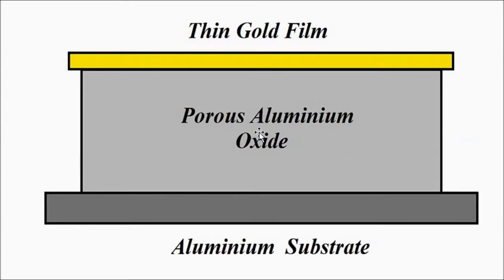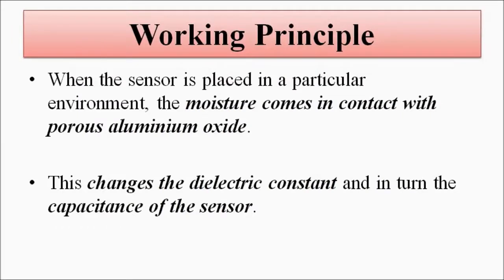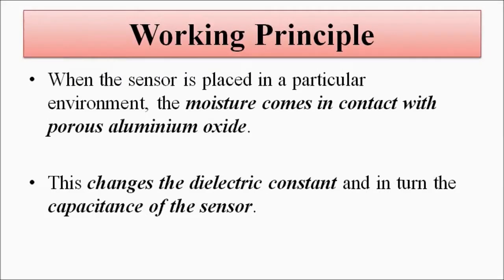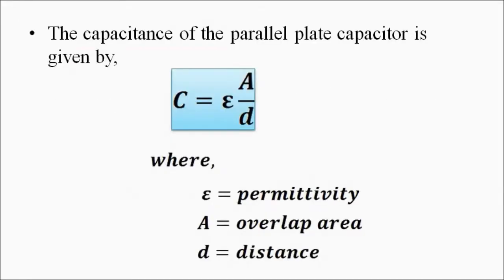The basic setup: the aluminum substrate acts as the base — one plate of the capacitor, one electrode — and the gold film is the other plate, with porous aluminum oxide between them. This is the sensitive material which responds to changing humidity or moisture levels. When this sensor is placed in a surrounding environment where humidity is to be measured, moisture comes in contact with the porous aluminum oxide, causing a change in permittivity or dielectric constant, which gives rise to a change in capacitance.